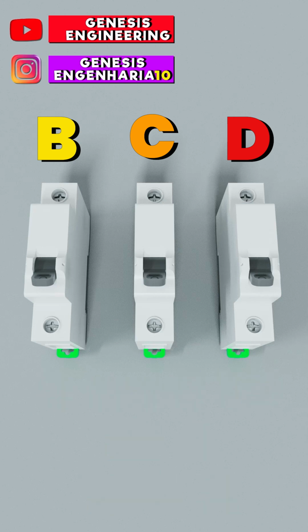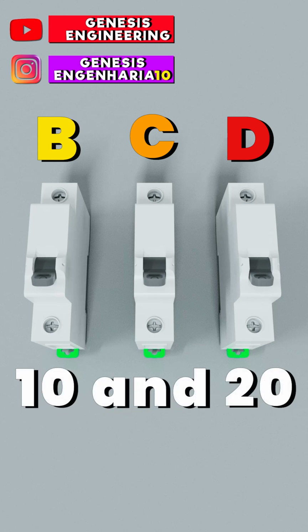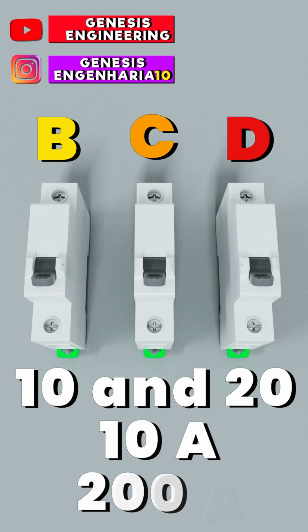The MCB with curve D, the supported current for short circuit protection, is between 10 and 20 times the rated current, so with a 10 amps MCB, it will withstand a short circuit current of maximum 200 amps.